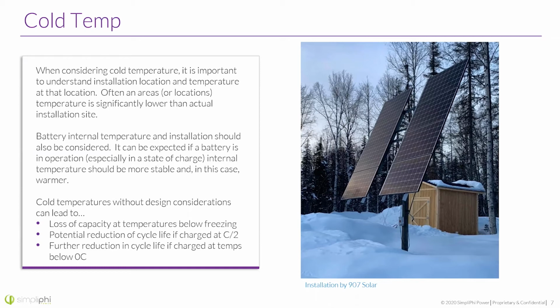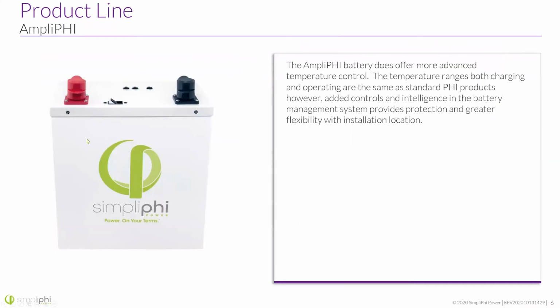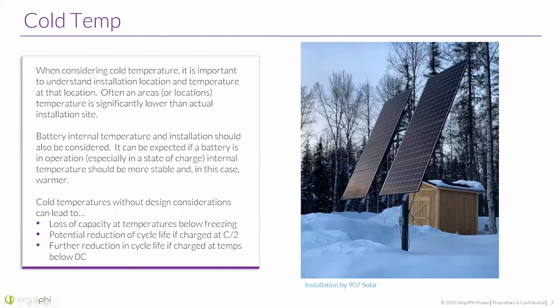So again, we don't need to just look at temperature outside. We really need to consider where the battery is going to be located and what that temperature will look like. We also should consider the battery's internal temperature. What I mean by this is, we look at the battery as a whole. This is just the case of the battery. Within it are the cells, and between that is some level of insulation and some other electronics that do keep fairly warm. The batteries themselves do run a little bit warm, not hot by any means, but they do run warm. So we can expect that the battery's internal temperature typically is going to be a little bit warmer than the outside temperature of that battery.